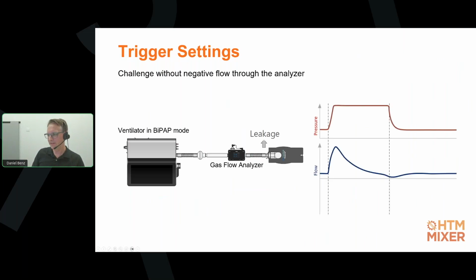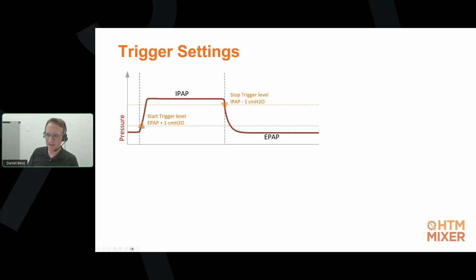And because of that, we will not have any negative flow through the gas flow analyzer. And in such a situation, you will see your flow waveform looks something like that, as we can see here on this slide. And here we don't have the signal changes that we want, so we cannot really trigger on the flow waveform. However, the pressure waveform has these nice slopes here actually. And typically in such a situation with BiPAP ventilators, you would choose the pressure waveform, and you would then set the start trigger on the pressure waveform, like here, for example, when it rises up. Typically, they call these two pressure levels IPAP and EPAP. So you will have your start trigger here, your end trigger here, and that is going to work perfectly fine.